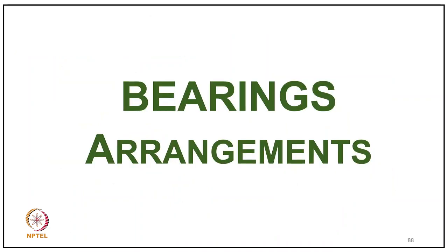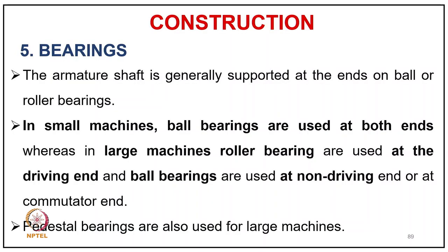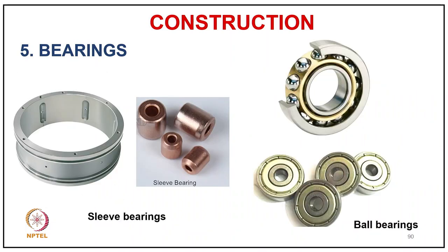The armature shaft is generally supported by ball or roller bearings. In small machines, ball bearings are used at both ends. In large machines, roller bearings are used at the driving end and ball bearings at the non-driving (commutator) end. Pedestal bearings are also used for large machines.